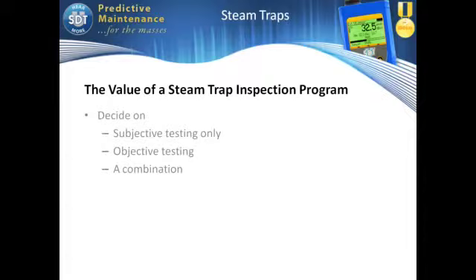For me, the great interest these days with steam trap testing is how to make that objective. How to, for example, capture a time signal, a dynamic signal of a steam trap, and say this is a good one, this is a bad one, because we can compare it with another one. So I think personally the combination of the 2 methods is my preferred way of working. Listening, and when I hear something that I'm not too sure about, then having the ability to dynamically record it and then process that signal. And it's really, really simple to do.